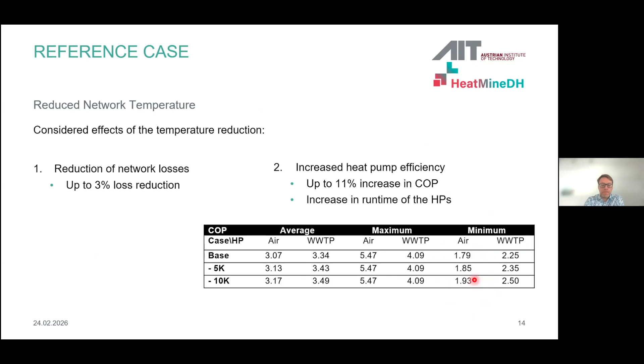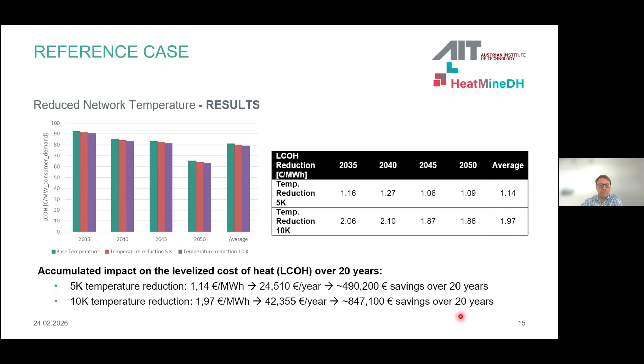This also affects the levelized cost of heat in euros per megawatt hour. So here you can see the LCOH for the base temperature in turquoise green color. The LCOH is expected to decrease over the years, and the temperature reduction also decreases the LCOH by an average of €1.14 for the 5K reduction and €1.97 for the 10K reduction. And this has a great effect. So it's around €24,000 per year for 5K reduction and €42,000 per year for a 10K reduction. And if you calculate it over the 20 years, it has a great effect in energy cost savings. So these were our results.